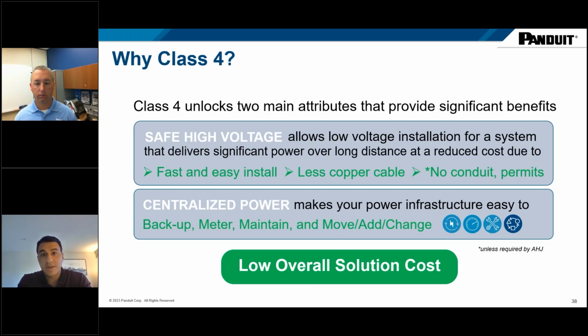And with that comes a lot of benefits. Obviously, we talked about how potentially a low voltage installer can install it, but even if an electrician is installing this, it's much faster and easier to install. You're using less copper cable. You don't have to run it in conduit, obviously based on jurisdiction rules. But these are a lot of the benefits that come from just that safe high voltage delivery.